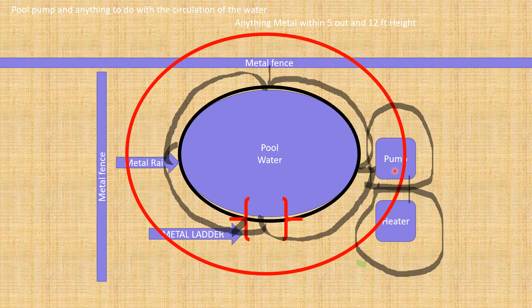So, you know, it's just something to think about. If I go ahead and make a ring around all this right here, I'm bringing it all to the same potential. So no matter where I'm standing, working on this pump, there's no less danger of being shocked right here or no less or no more than there is right here. So if I'm standing over here, I'm at the same danger as if I was standing right here. So having the equipotential bond out here is something to consider.